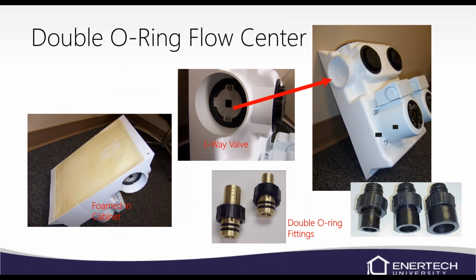Again, we use double O-ring. There are the double O-ring fittings on the left, the double O-ring fitting to the unit, so that would be a hose barb. And then on the right, those are actually the fittings for the loop field, the PE pipe, the HDPE pipe there. The flow centers, they're black now, not white like this, but other than the color, they're the same. You've got your 3-way valve, it's got a foamed cabinet on the back.